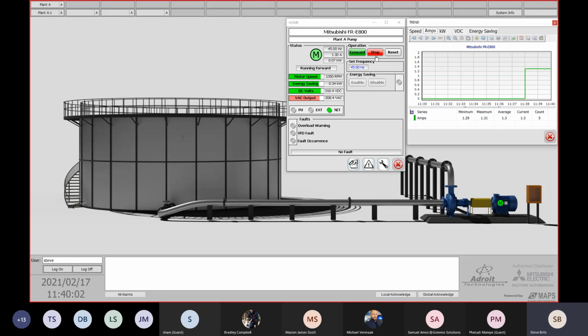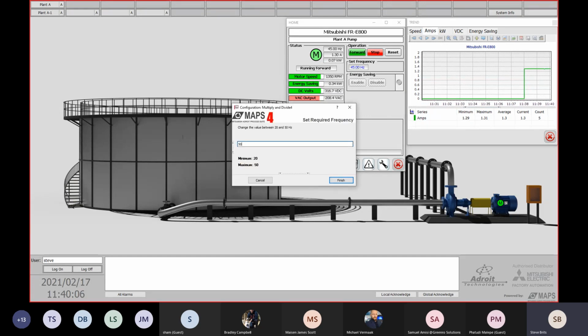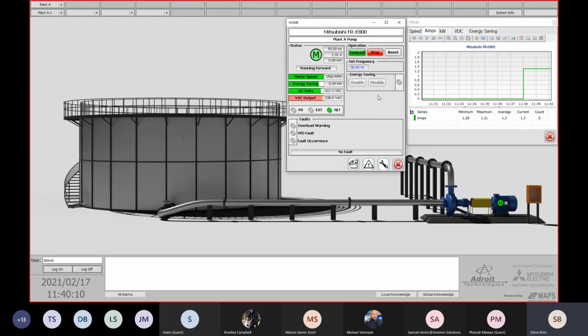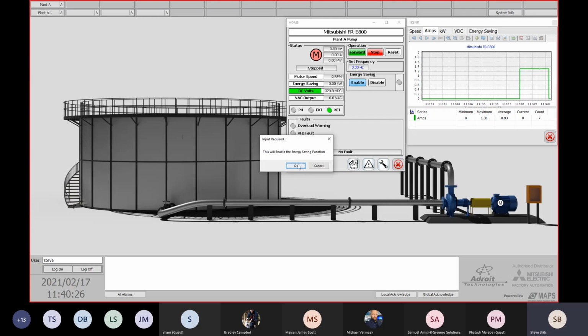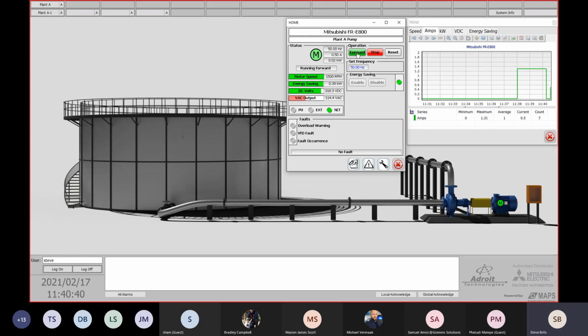If I now stop the motor, let's first ramp it up back to 50 Hertz. And we can see our voltage output at 230 volt. We're going to stop it. So once I've stopped, my energy saving function to enable it becomes available, as there's certain parameters you can't change on the drive while it's running. And now I'm going to start it forward again. Now, with the previous setting, I believe most of you could hear the motor running in the background. Now the motor is running a lot quieter. As you can see, I'm back running at 50 Hertz on my graph, and on my faceplate I get the feedback from the drive for 50 Hertz.